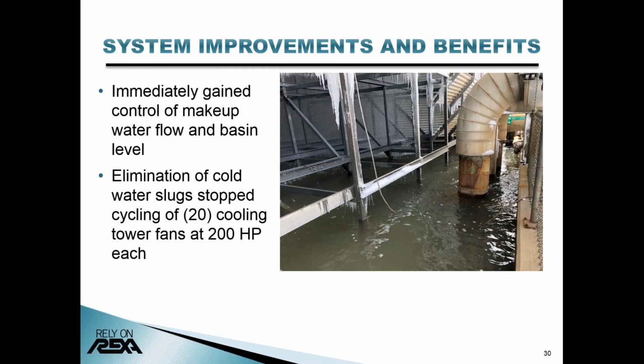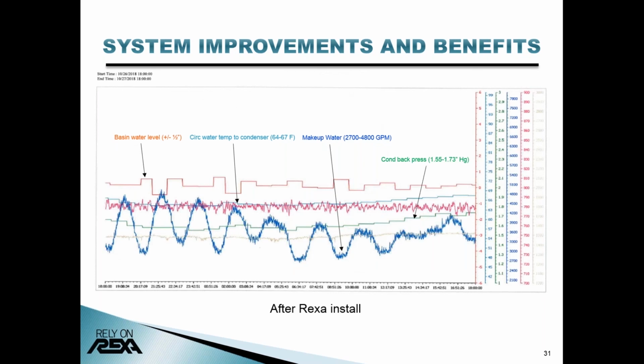Wow, and I can see you have 20 of those cooling tower fans at 200 horsepower apiece. That's 4,000 horsepower worth of fans that were starting and stopping several times an hour. Wow. Well, all right then. This next set of graphs is from about 2 years after the REXA actuator was installed. These look considerably different from the previous graphs. Buddy, can you explain to us what's going on in this slide?